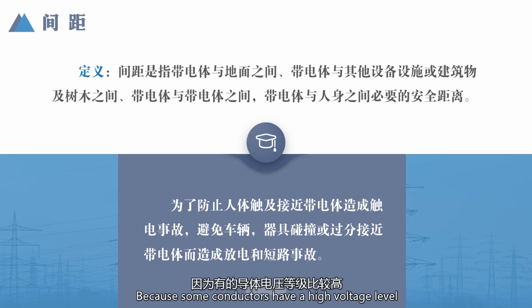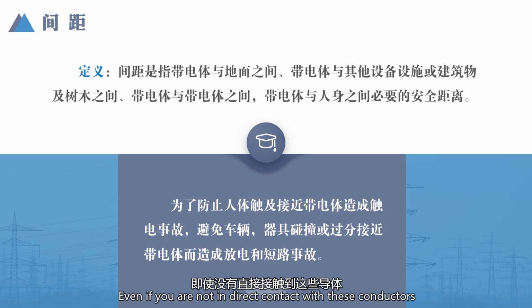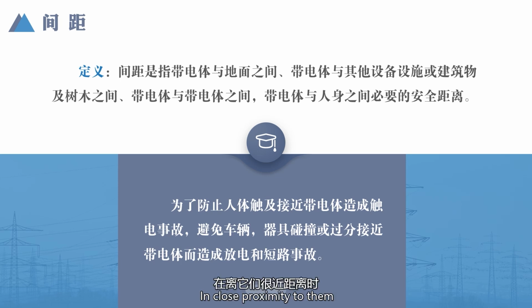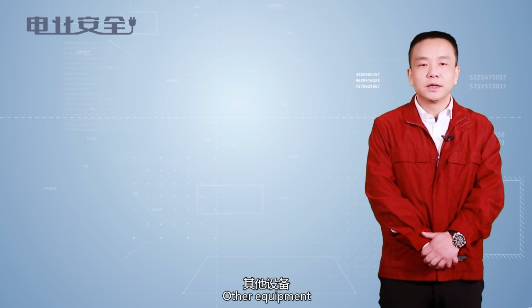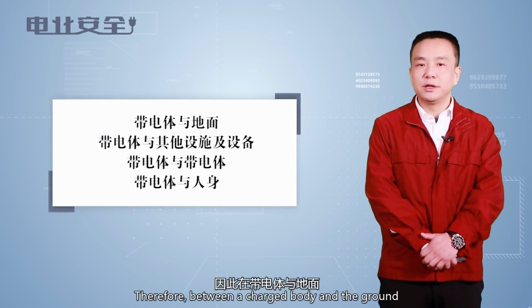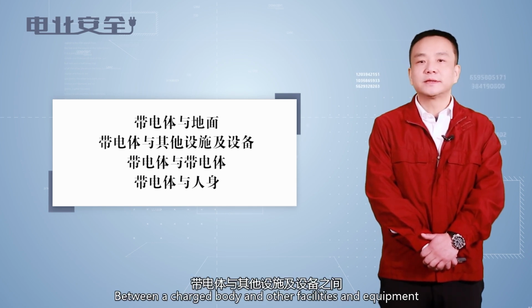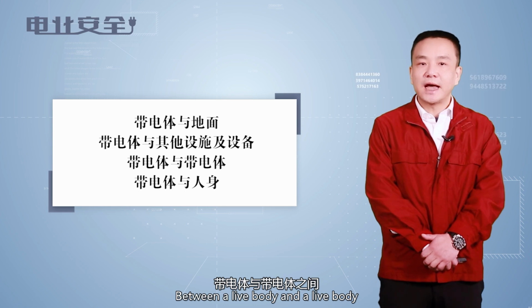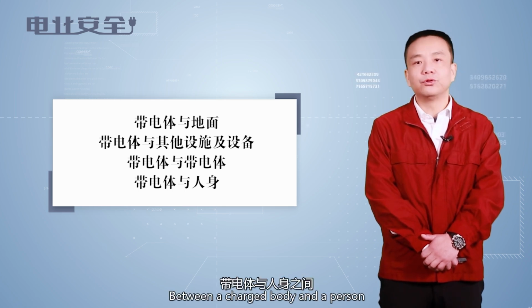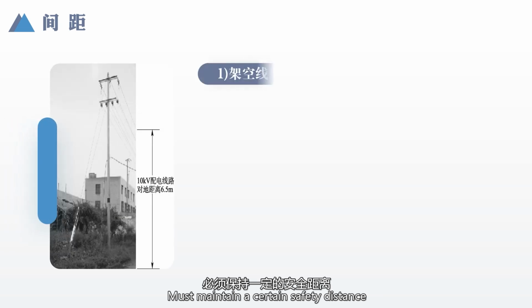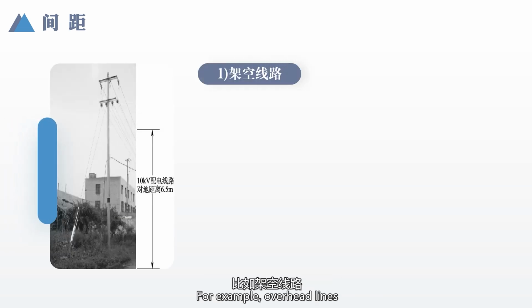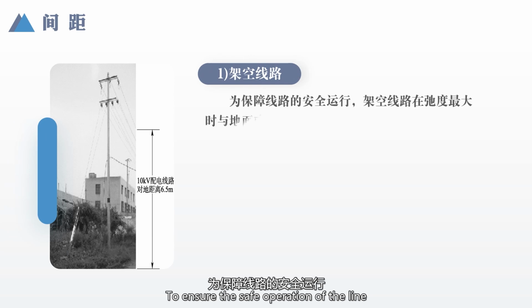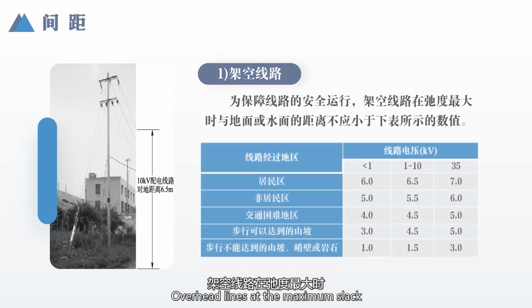Here we should pay attention: because some conductors have a high voltage level, even if you are not in direct contact with these conductors, being in close proximity to them can still cause a short circuit or discharge from the charged body to the human body or other equipment. Therefore, between a charged body and the ground, between a charged body and other facilities and equipment, between a live body and a live body, and between a charged body and a person, a certain safety distance must be maintained, for example, for overhead lines.